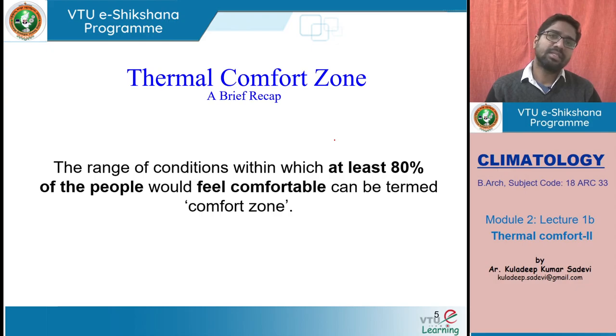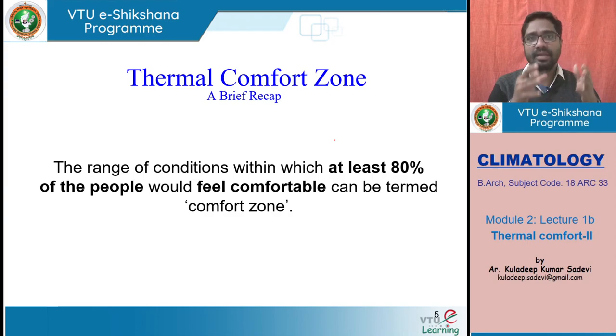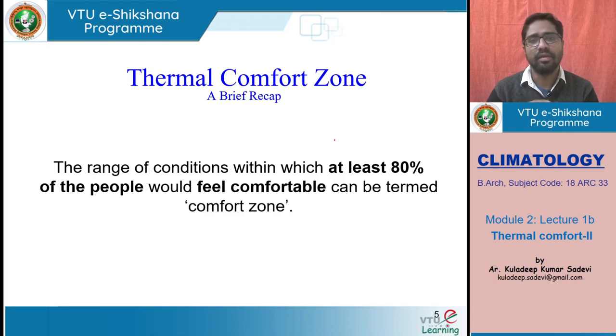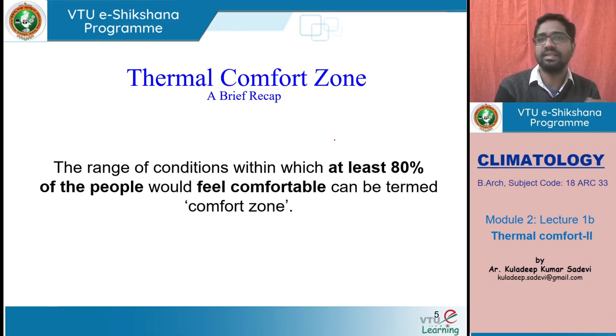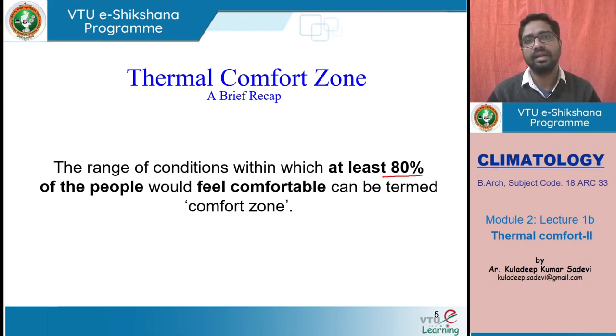So we have discussed what is comfort and what makes a user comfortable. Now we will see what is called thermal comfort zone. When we say zone here, there is a wide range of temperatures and humidity levels — dry bulb, wet bulb, and globe thermometer for radiation. At what particular conditions a person can feel comfortable is what we define as comfort zone. The definition says: the range of conditions at which at least 80 percent of the people would feel comfortable. This common scenario is considered to be the thermal comfort zone.